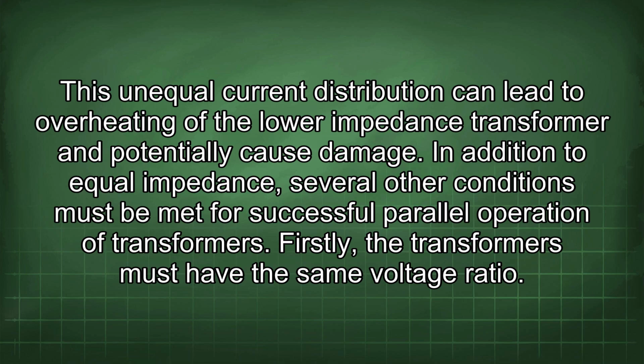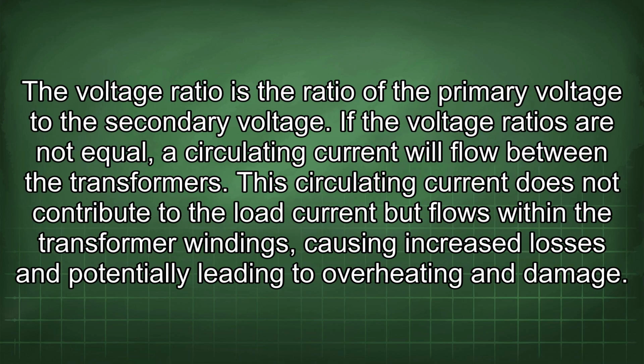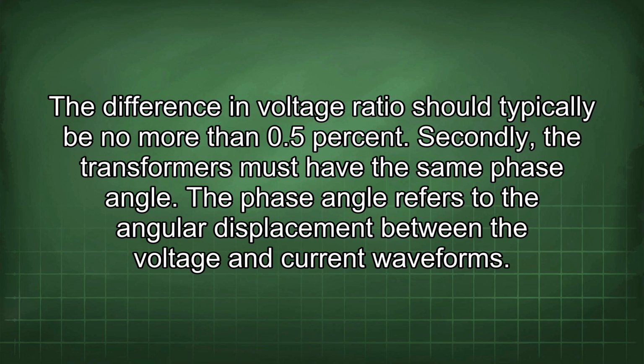In addition to equal impedance, several other conditions must be met for successful parallel operation of transformers. Firstly, the transformers must have the same voltage ratio. The voltage ratio is the ratio of the primary voltage to the secondary voltage. If the voltage ratios are not equal, a circulating current will flow between the transformers. This circulating current does not contribute to the load current but flows within the transformer windings, causing increased losses and potentially leading to overheating and damage. The difference in voltage ratio should typically be no more than 0.5%.